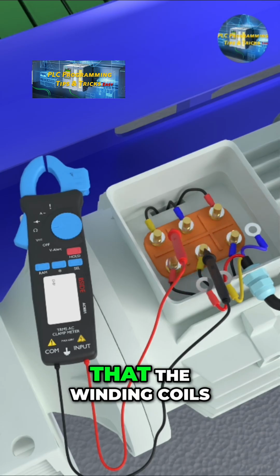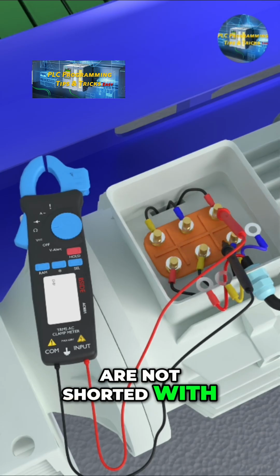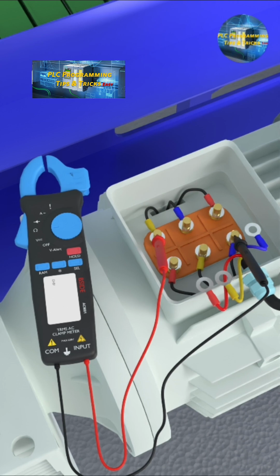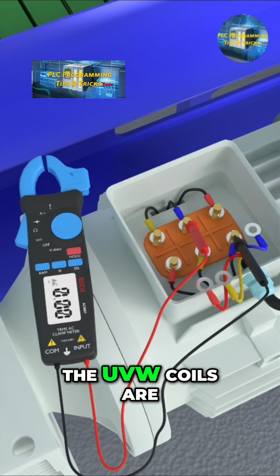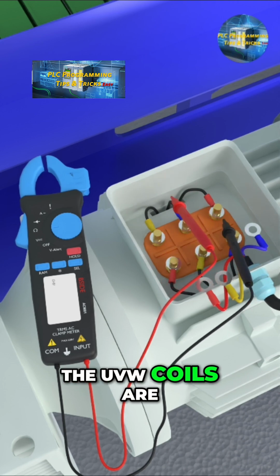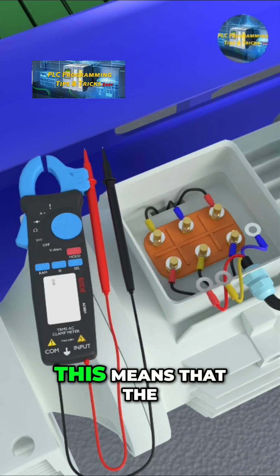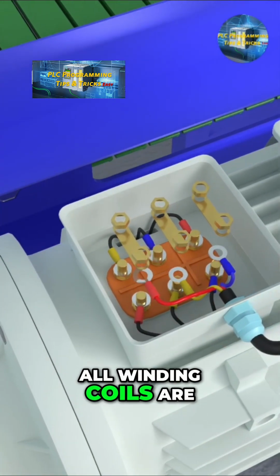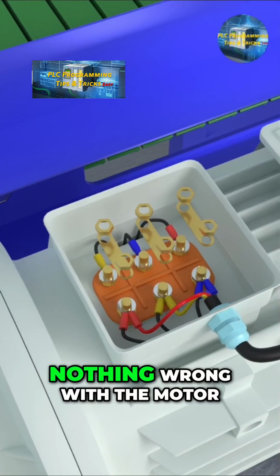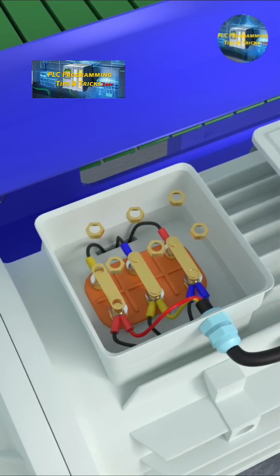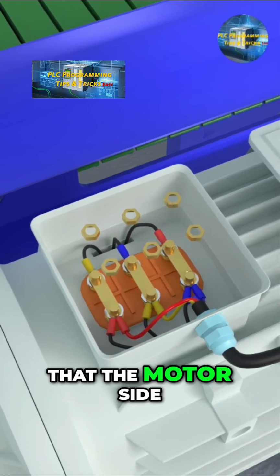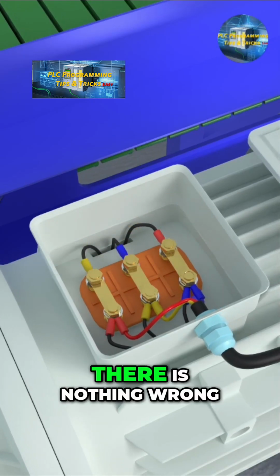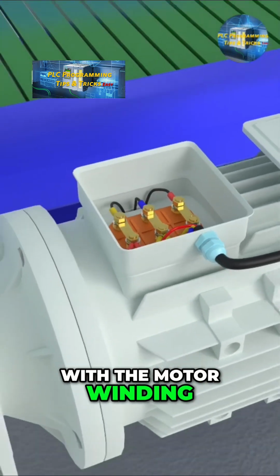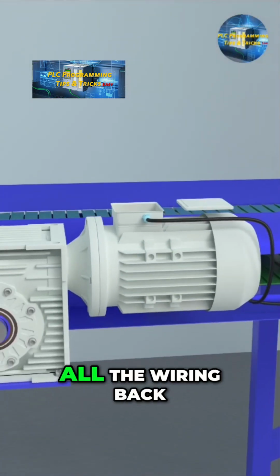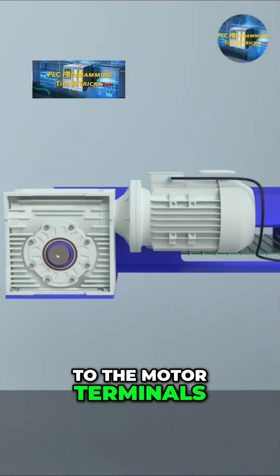As you can see, the winding coils are not shorted with each other. Also, the ends of the U, V, W coils are showing continuity. This means that all winding coils are fine and there is nothing wrong with the motor. Now we have checked that the motor side is okay. There is nothing wrong with the motor winding. So we will connect all the wiring back to the motor terminals.